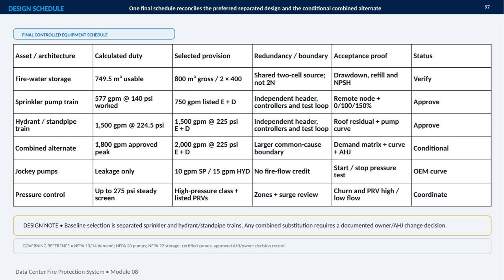The sprinkler train is selected at 750 gallons per minute, and the hydrant and standpipe train at 1,500 gallons per minute and 225 psi. Both require performance testing, including remote node or roof residual verification and pump curve confirmation. The combined alternate increases capacity to 2,000 gallons per minute, but it also creates a larger common cause boundary, so it remains conditional on the demand matrix, hydraulic curve, and an owner or AHJ decision. Jockey pumps receive no fire flow credit, and pressure control requires high-pressure equipment, listed PRVs, zoning, and surge review. Final acceptance follows the applicable NFPA standards and certified equipment data.